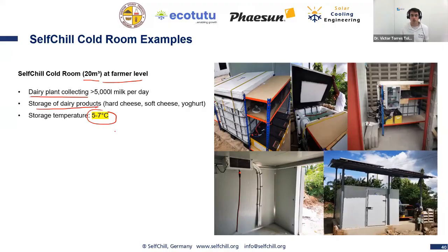That's why this cold room is working at this temperature, because in Tanzania, near Dar es Salaam, the ambient temperatures are so high. This cold room has a higher insulation. We are working here with 100 millimeters insulation thickness. You see here the heat exchanger, the PV panels on top, the cold cell here, and here you see the ice storage. This one has been produced with an IBC container and polystyrene plate.